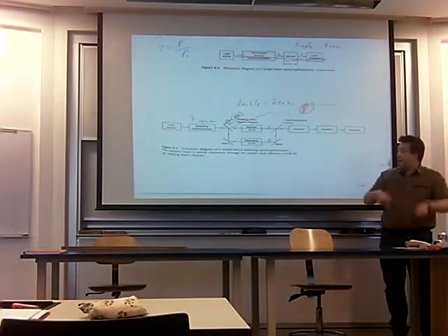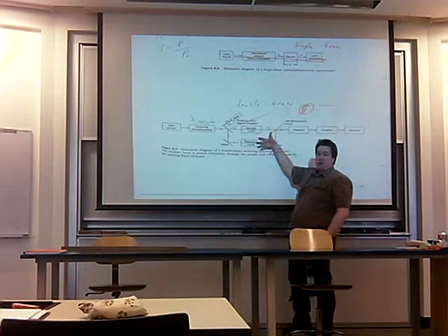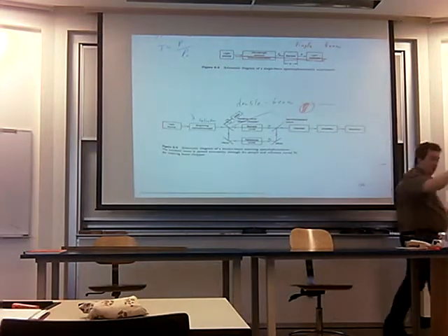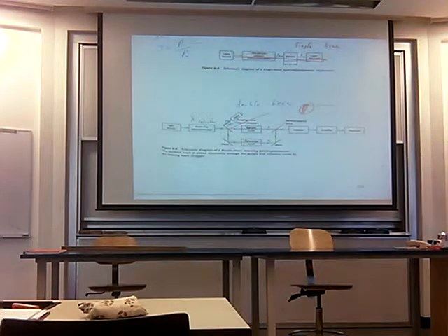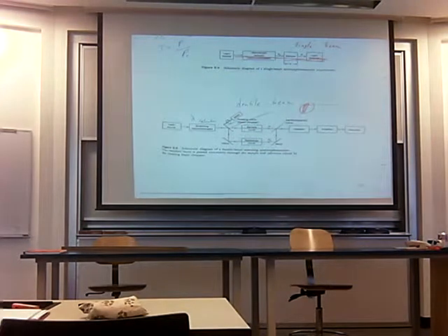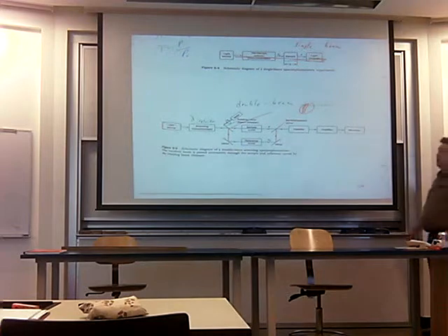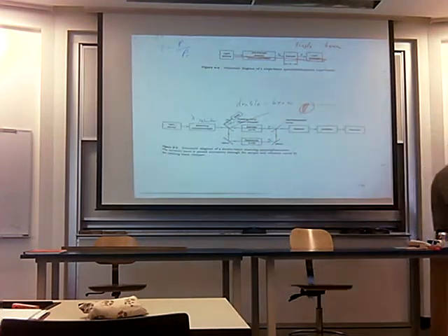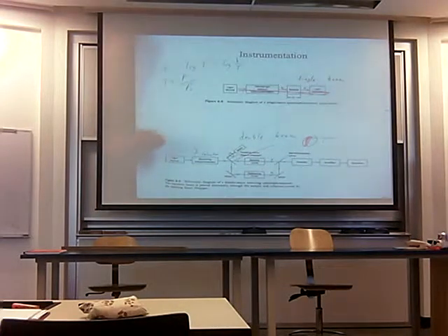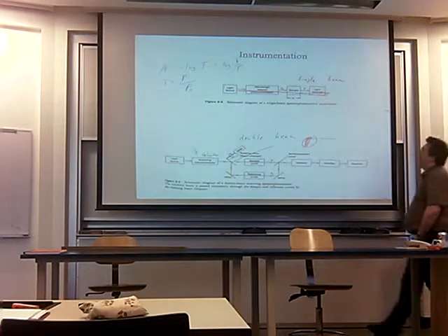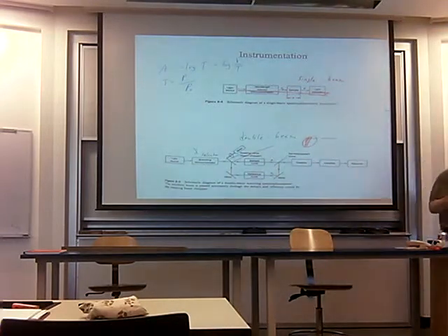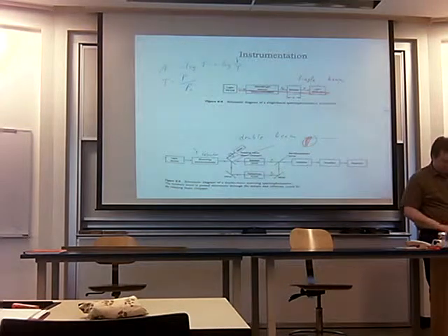But in that case, if you only used one cuvette, you were essentially blanking on air, because the light was alternating, going back and forth between the front and back. So if you didn't put anything in the back reference cell, it was automatically referencing to air. So you've used double beams in that case. You will in lab today, tomorrow, Thursday, this week, be using a single beam instrument. I'll use it a couple of times over this time.